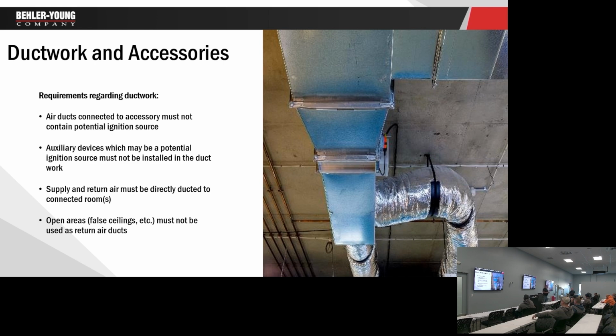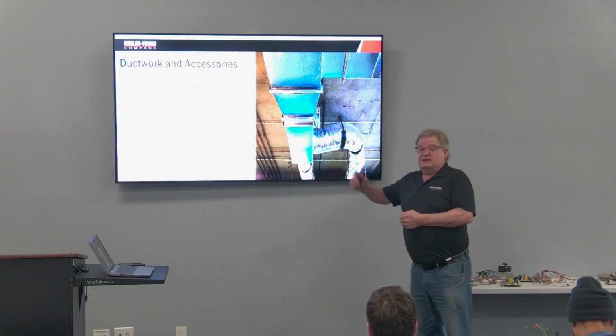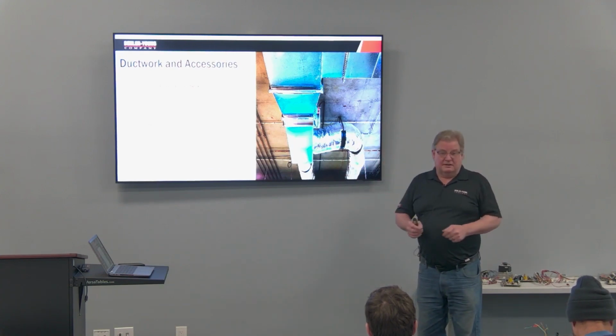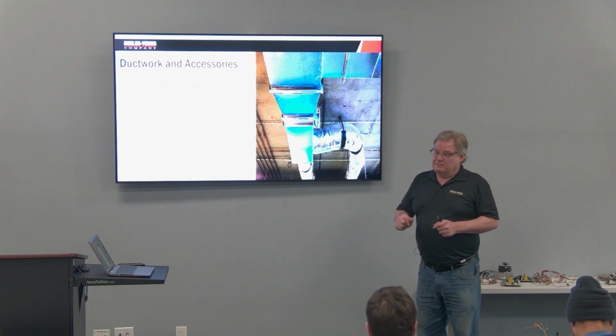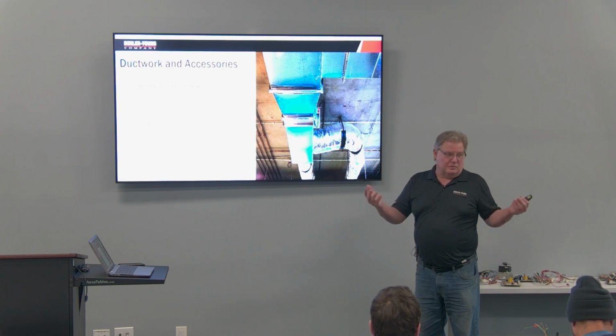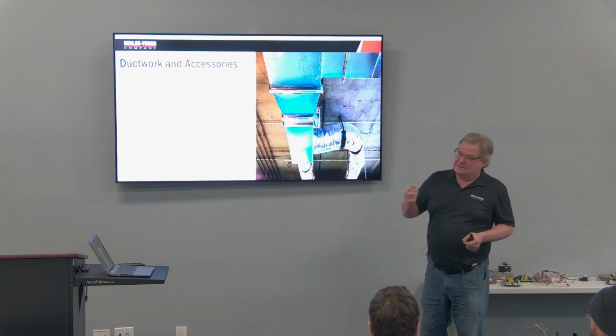Okay, you do have to have a fire extinguisher in your truck now. That is a DOT requirement. You don't need to placard your trucks unless you carry more than 440 pounds of A2L in your truck. Somebody asked about the tank. The tank does have a reverse thread on it, so you're going to need an adapter. It's got a red stripe on the tank. The recovery cylinder has a red stripe on it. The unit still has 1/4 inch flare, so we'll talk about tools when we get to that part. But the hoses you currently use will work. The only backward thread is on the tank itself.